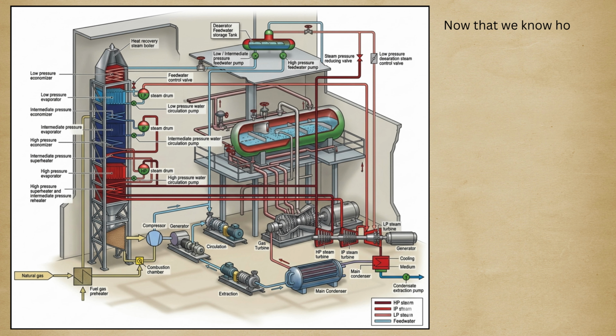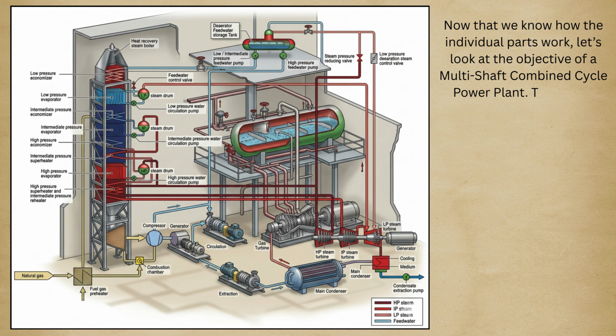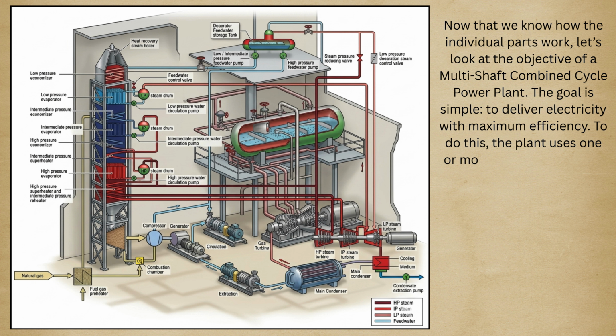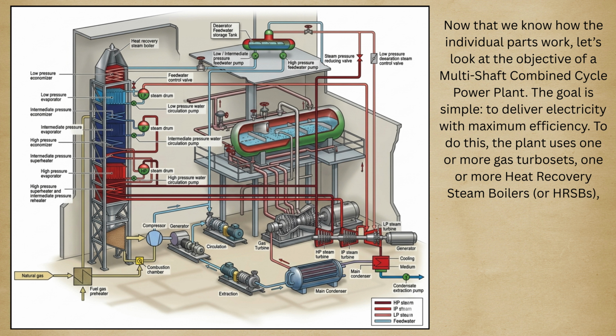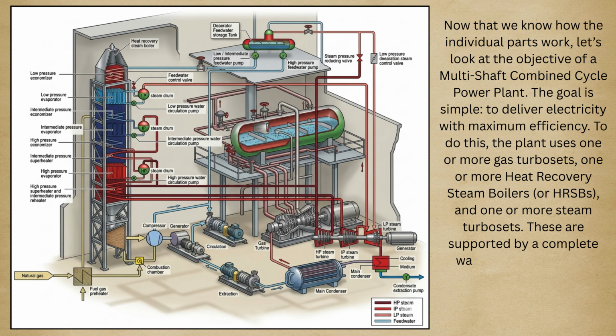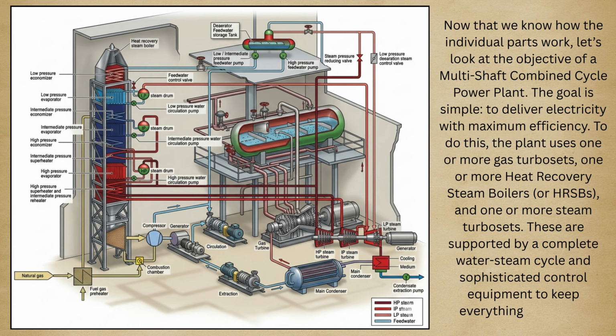Now that we know how the individual parts work, let's look at the objective of a multi-shaft combined cycle power plant. The goal is simple: to deliver electricity with maximum efficiency. To do this, the plant uses one or more gas turbosets, one or more heat recovery steam boilers, or HRSBs, and one or more steam turbosets. These are supported by a complete water steam cycle and sophisticated control equipment to keep everything in balance.